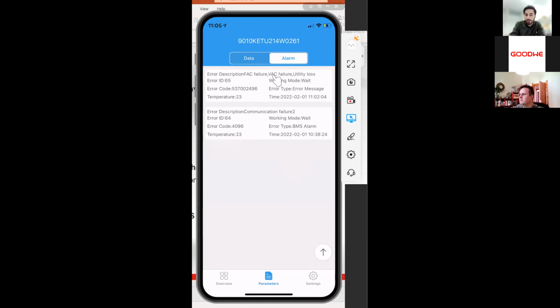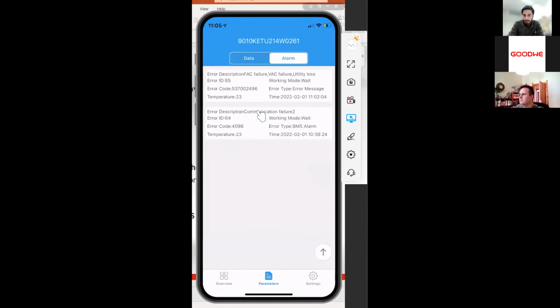frequency AC failure, volt AC failure, utility loss. Utility loss usually means that the AC side is not connected. That also makes sense because we are not connected there. Sorry. And now to set it up, we press on settings.